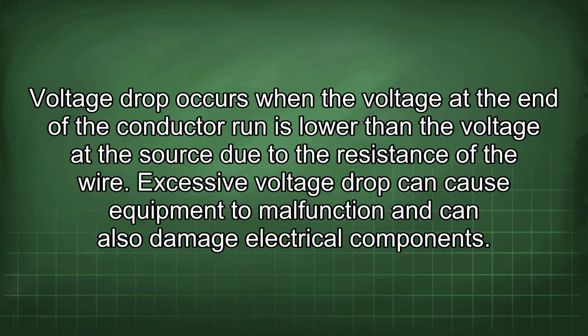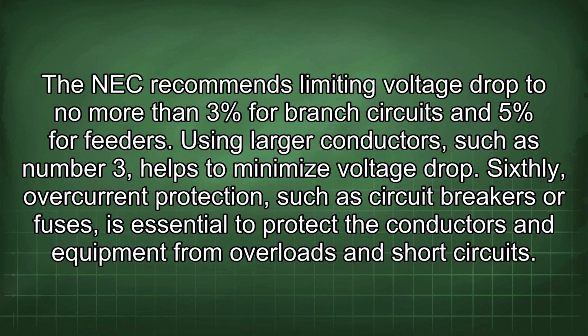Voltage drop occurs when the voltage at the end of the conductor run is lower than the voltage at the source due to the resistance of the wire. Excessive voltage drop can cause equipment to malfunction and can also damage electrical components. The NEC recommends limiting voltage drop to no more than 3% for branch circuits and 5% for feeders.